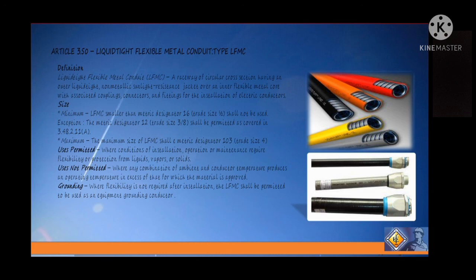And for the exception, metric designator 12, the trade size of 3/8, shall be permitted as covered in section 3.48.2.11a. And for the maximum, the maximum size of LFMC shall be metric designator 103 or trade size number 4. For uses permitted, where conditions of installation, operation, or maintenance require flexibility or protection from liquids, vapors, or solids. For uses not permitted naman, where a combination of ambient and conductor temperature produces an operating temperature in excess of that for which the material is approved.